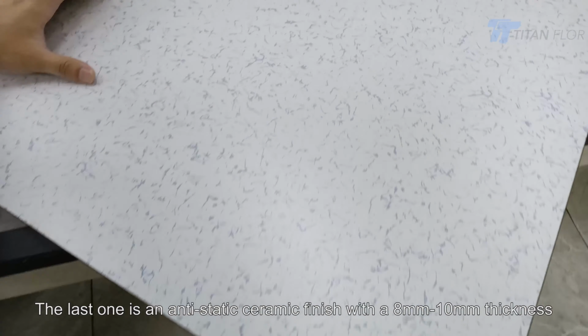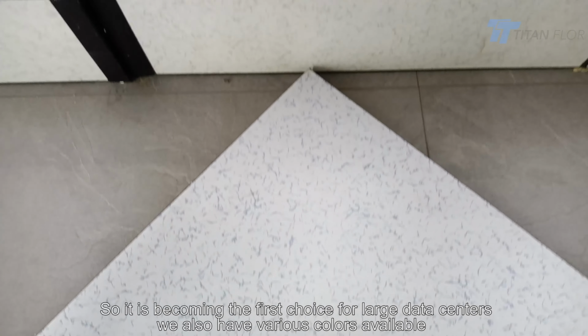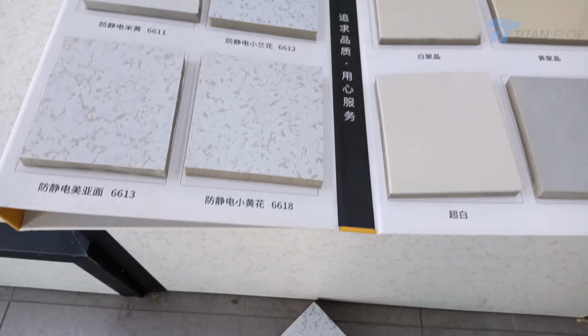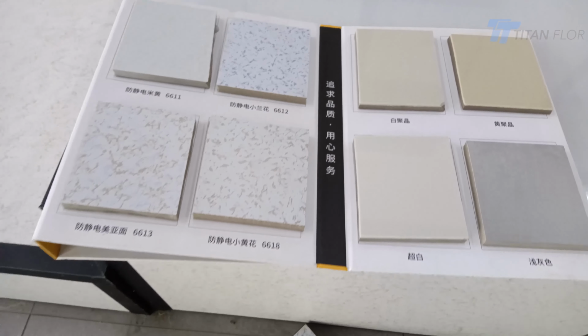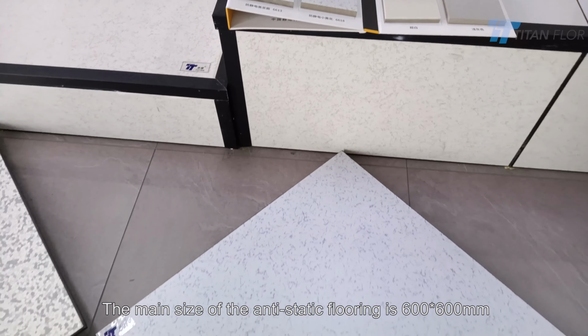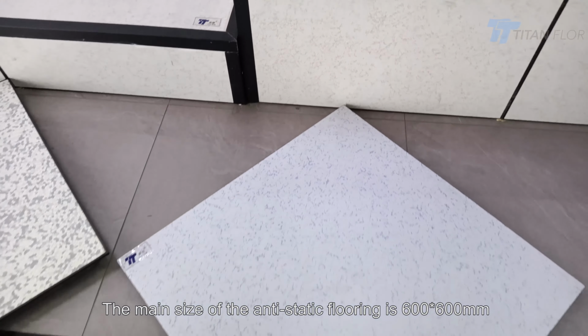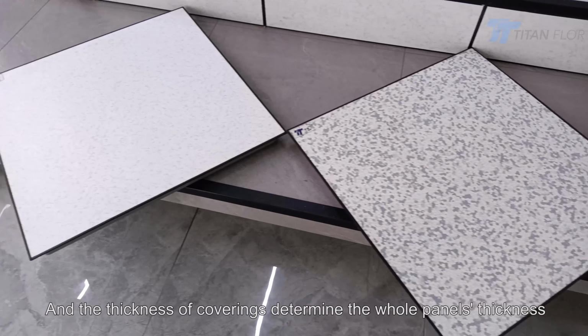The last one is an anti-static ceramic finish with an 8 to 10 mm thickness. As ceramic is not affected by temperature, it will not have crack problems like HPL. So it is becoming the first choice for large data centers. We also have various colors available. The main size of this anti-static flooring is 600 mm, and the thickness of coverings determines the whole panel thickness.